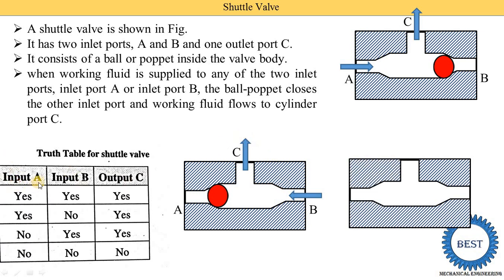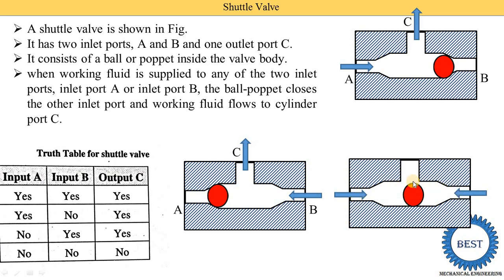The third case in the table — case one — is when fluid is input from both ports A and B simultaneously. When we supply fluid from both A and B at the same pressure, the ball comes to the center and fluid passes through the passage to outlet C, and from port C it is supplied to the actuators.